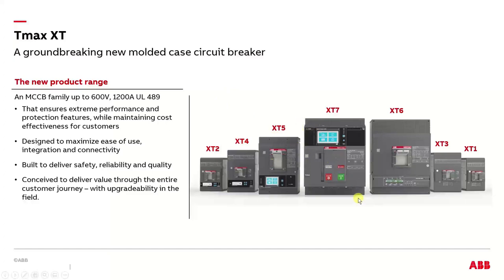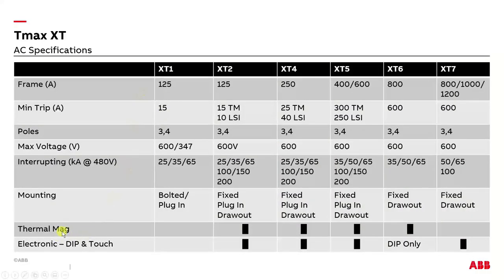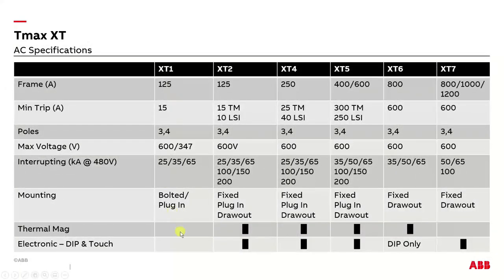this is our flagship line of breakers that we've just released starting last year. And we have a full range of molded case up to 1200 amps, which would be our XT7. Here's a table, and the important thing to take from the table is that almost all these breakers are available in thermomagnetic and solid state. This is electronic, would be solid state. So there's actually a mistake here, because this XT1 is thermomagnetic. I'll go back. This XT1 breaker is thermomagnetic only, and it doesn't come in an electronic version.